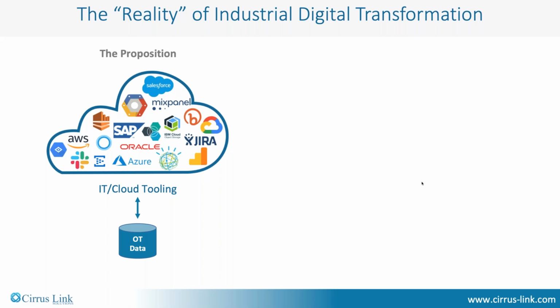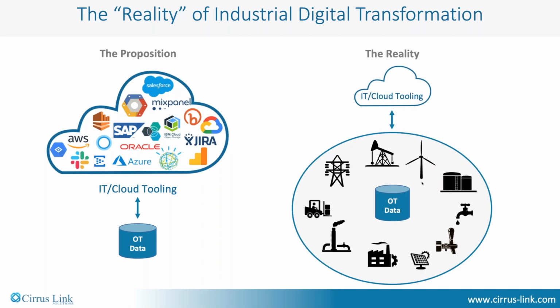And then we've got this little line down to OT data. And that's really not their fault - it's not their fault that a 20-year-old Modicon PLC won't interface to the cloud. But that's the reality. So the proposition is we've got all this possibility, but the reality is that getting the OT data without disrupting an operational system at the same time is crucial.